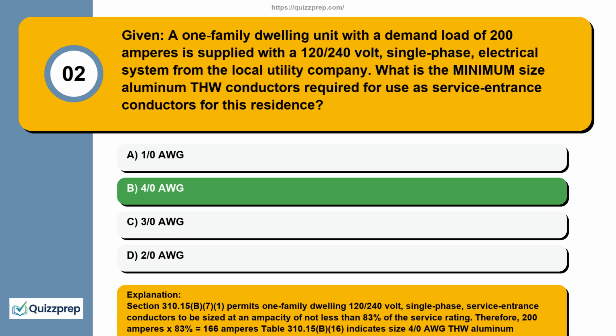Section 310.15(B)(7)(1) permits one-family dwelling 120/240 volt, single-phase, service entrance conductors to be sized at an ampacity of not less than 83% of the service rating. Therefore, 200 amperes x 83% equals 166 amperes. Table 310.15(B)(16) indicates size 4/0 AWG aluminum conductors with an allowable ampacity of 180 amperes should be selected for this dwelling.